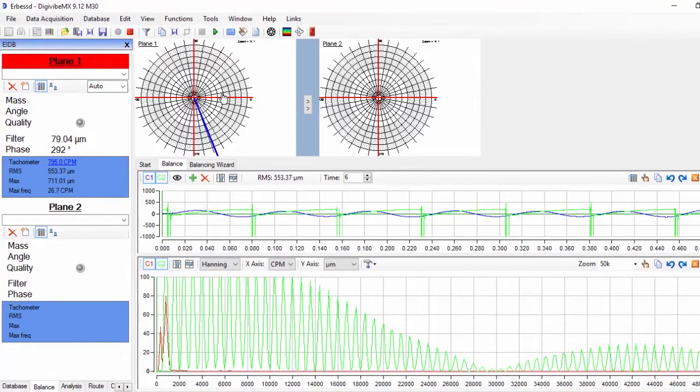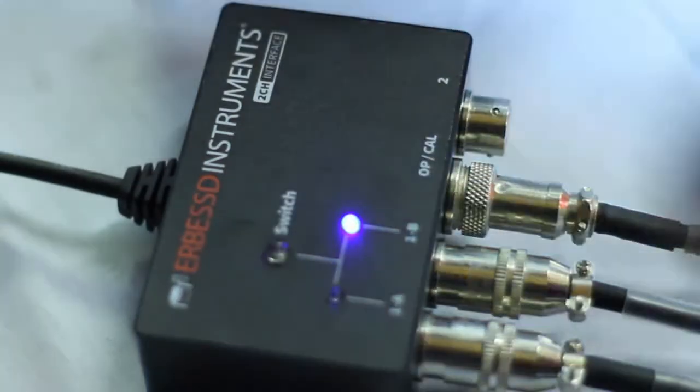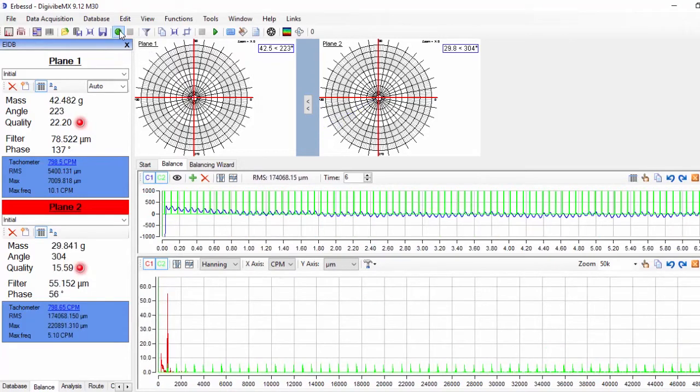We record the signal from plane 1, and once the recording is finished the signal will appear on the central window. We press the switch button on the interface to select plane 2, and we also select plane 2 on the DigivibeMX by clicking on the right polar graph or plane 2 on the left column, and we start the recording.